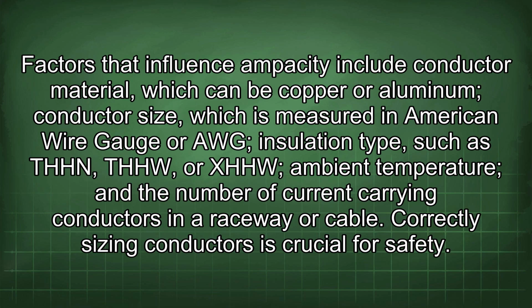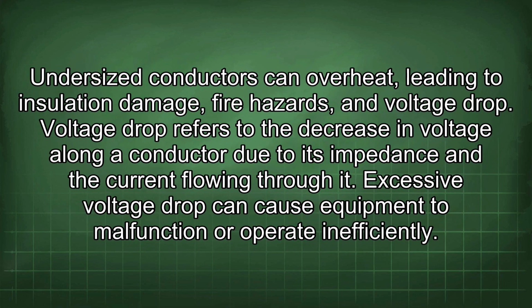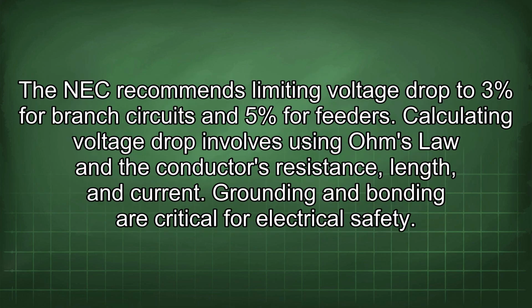Correctly sizing conductors is crucial for safety. Undersized conductors can overheat, leading to insulation damage, fire hazards, and voltage drop. Voltage drop refers to the decrease in voltage along a conductor due to its impedance and the current flowing through it. Excessive voltage drop can cause equipment to malfunction or operate inefficiently. The NEC recommends limiting voltage drop to 3% for branch circuits and 5% for feeders. Calculating voltage drop involves using Ohm's law on the conductor's resistance, length, and current.